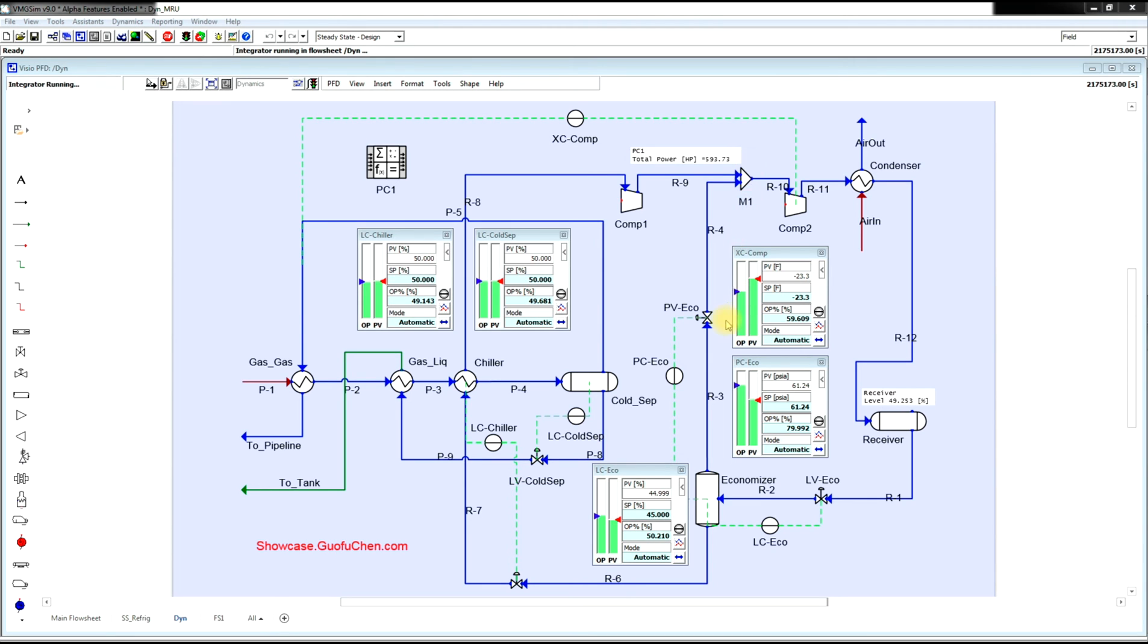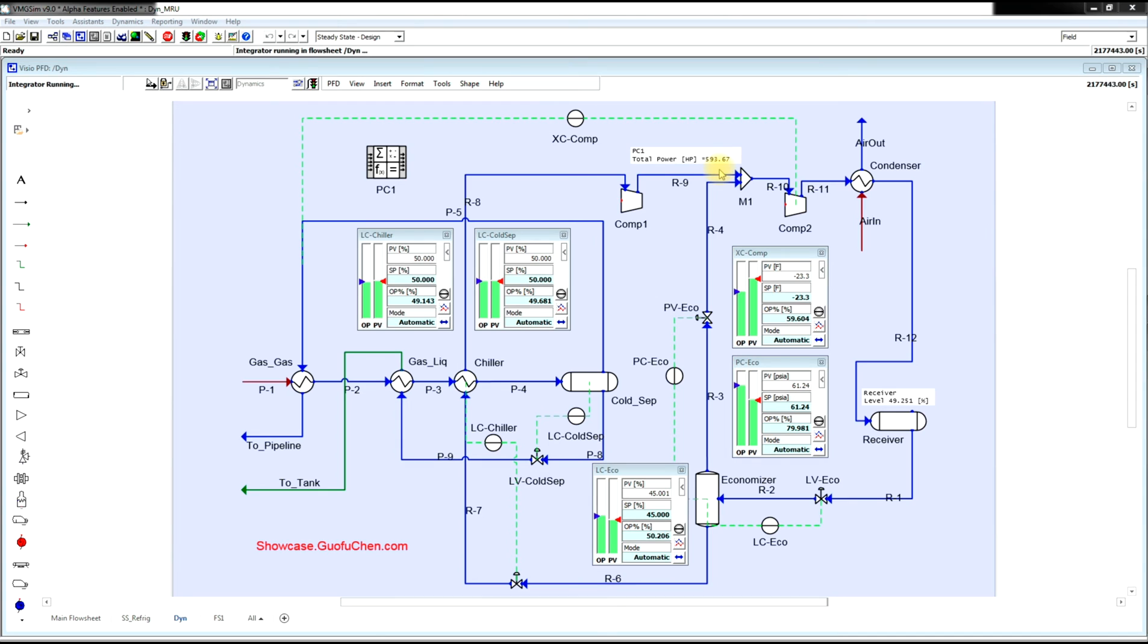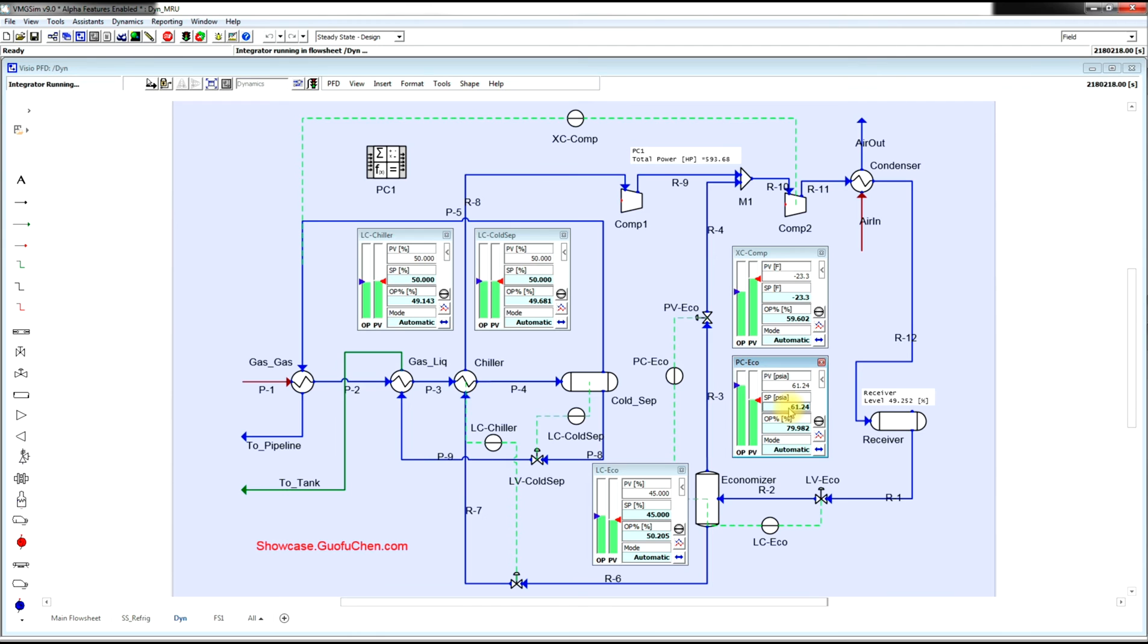Can I save some energy on the compressor? Currently, the power consumption is about 594 horsepower. Let me try to set the economizer pressure to 70 psi.